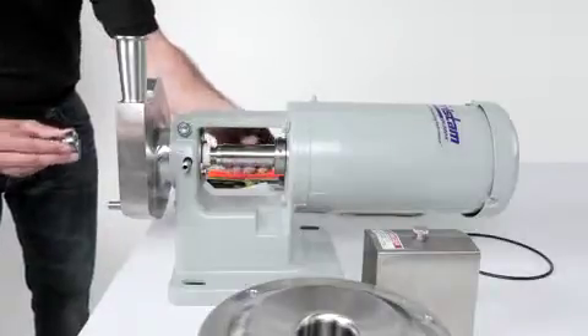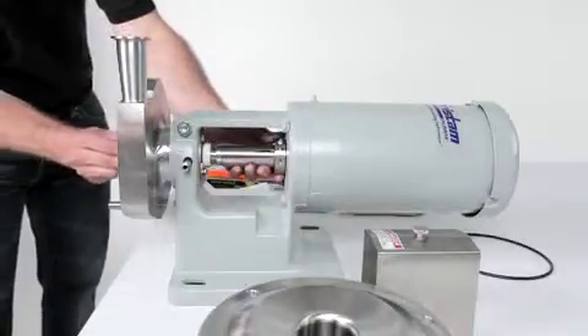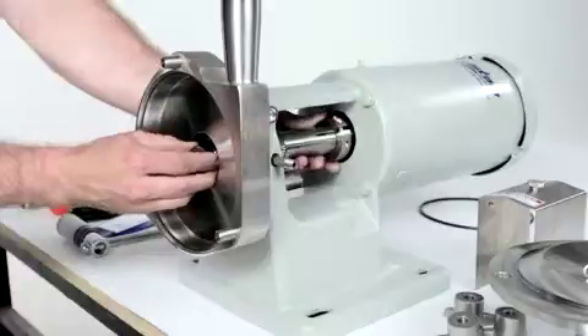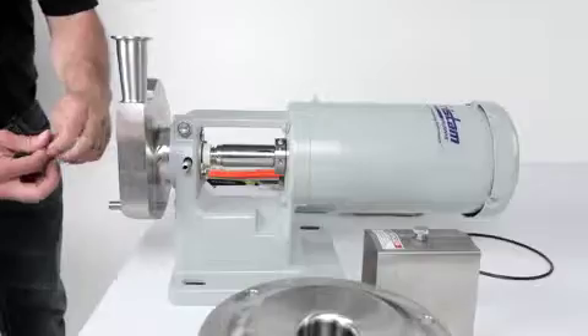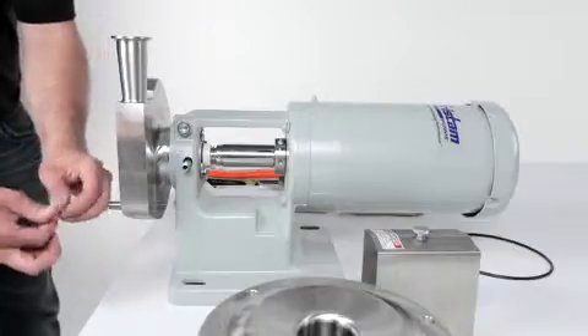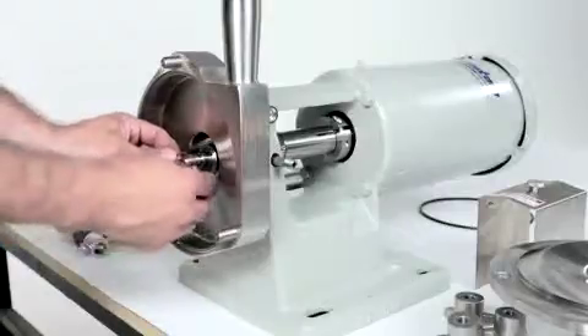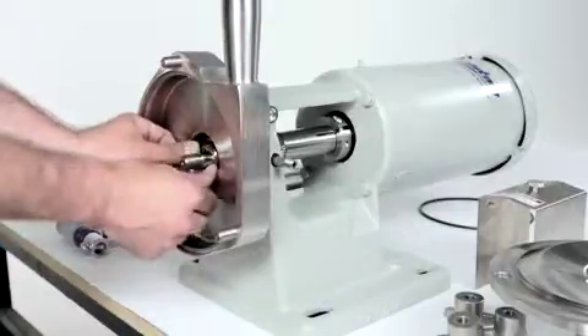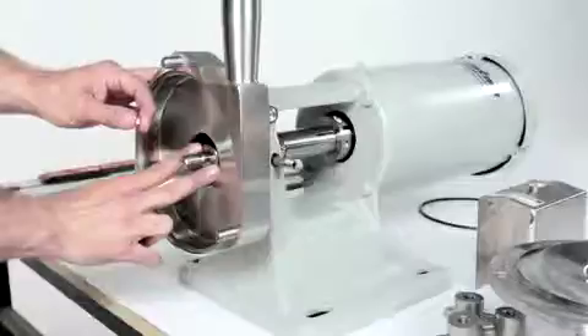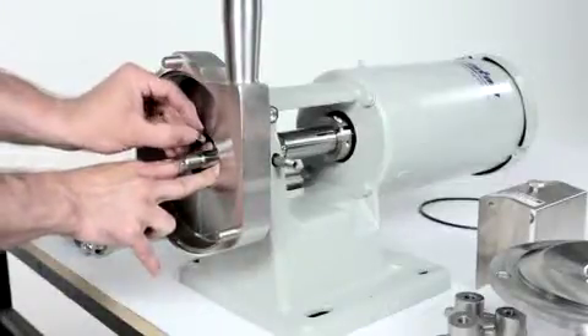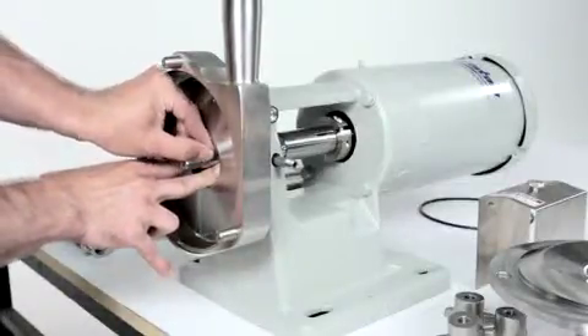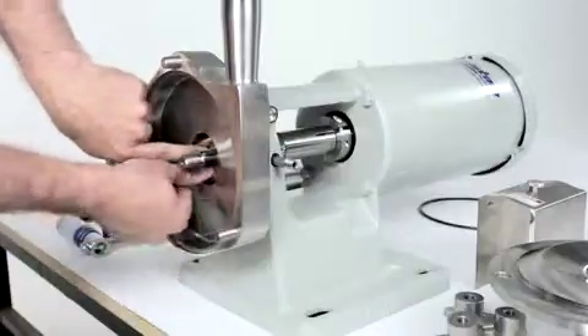Rotate the pump shaft so the keyway is on top. Now slide the rotating seal assembly onto the pump shaft. Lubricate the outside O-ring and install it in the groove on the front of the seal spring and driver assembly. Compress the spring assembly with 2 fingers and install the impeller key into the keyway on the pump shaft.